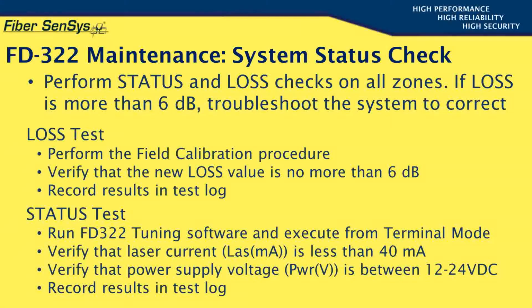To perform the status test, use the APU's terminal mode. Verify that the laser current is less than 40 milliamps and that the power supply voltage is between 12 and 24 volts DC, and record the results in the test logbook.